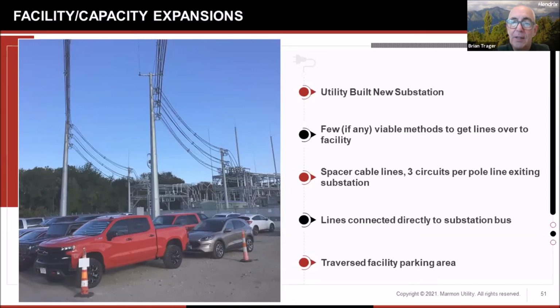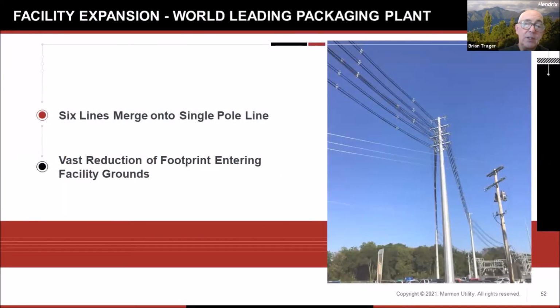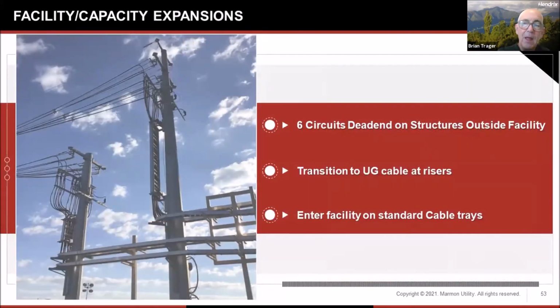So we put 3 spacer cable lines on 2 poles. So we had 6 circuits on 2 poles. Those lines connected directly to the substation bus. And at that point, we started traversing the parking area. As we got closer to the facility in question, we merged those 6 lines onto a single pole line, and that resulted in a vast reduction of the 100 megawatt feed footprint entering the facility grounds. We dead ended those 6 circuits on 2 structures outside of the facility, and we transitioned to underground cable at the risers. And you can see we entered the facility on, again, standard underground cable trays.